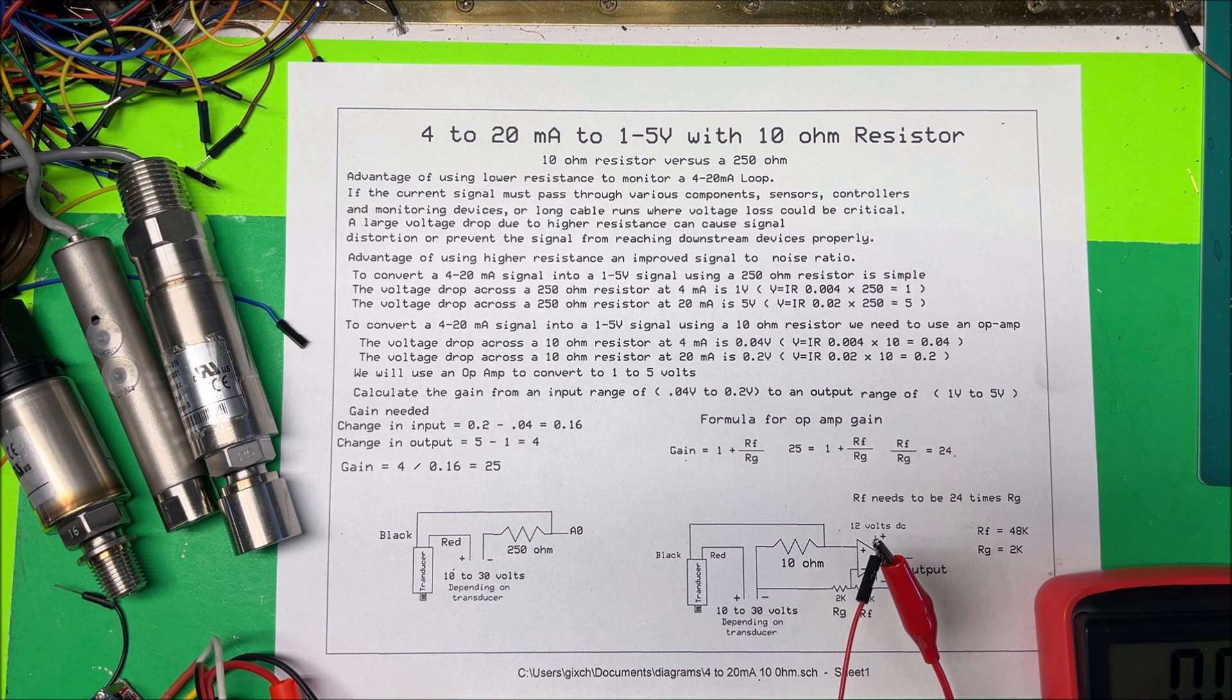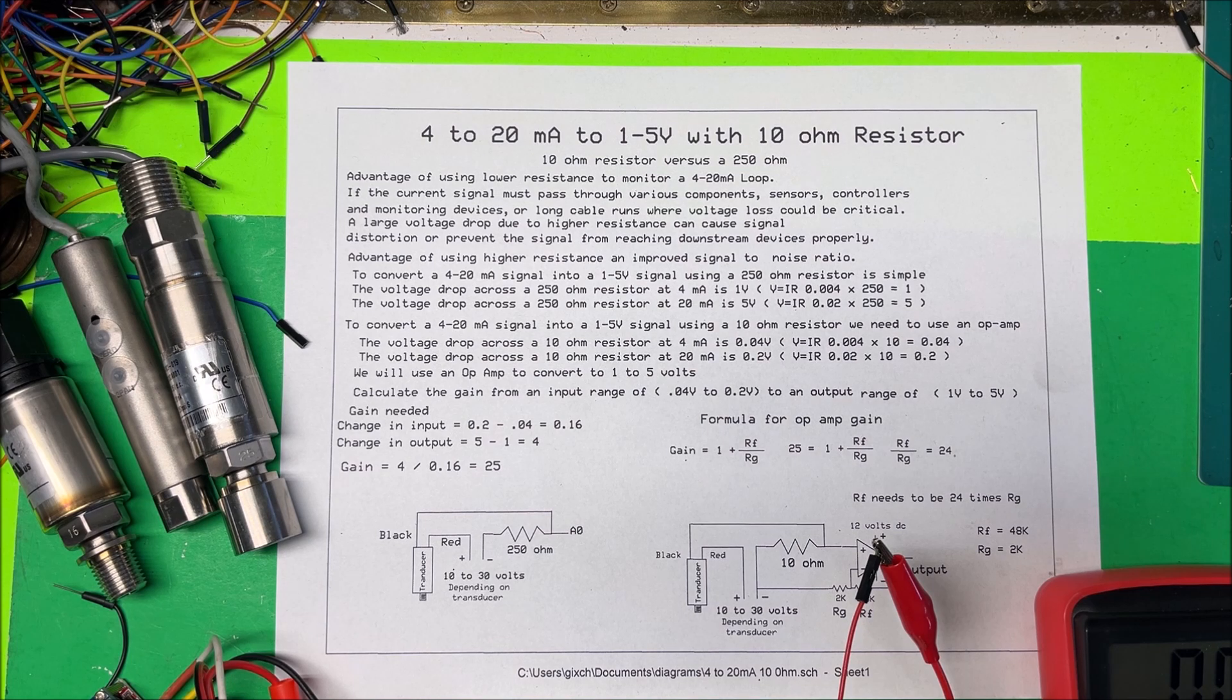Because if you use a 250 ohm resistor, 4 milliamps into 250 ohms gives you 1 volt, and 20 milliamps into 250 ohms gives you 5 volts, so you're all set to go. Here's a diagram to use to do it that way. You've got your transducer here.